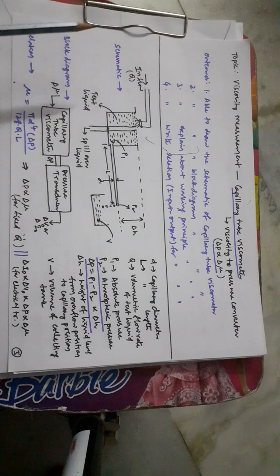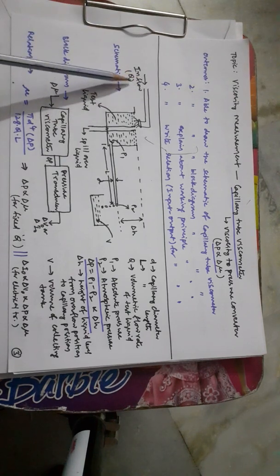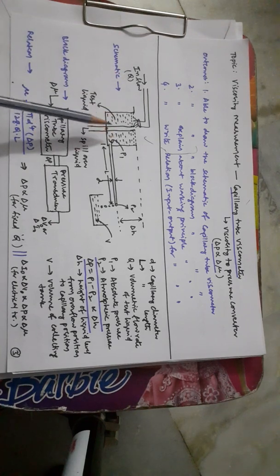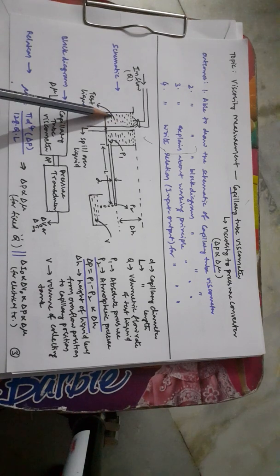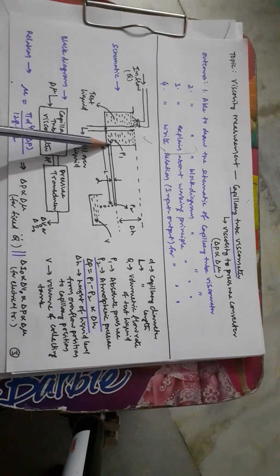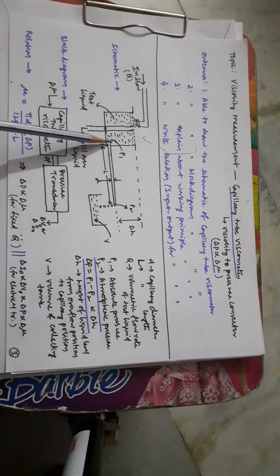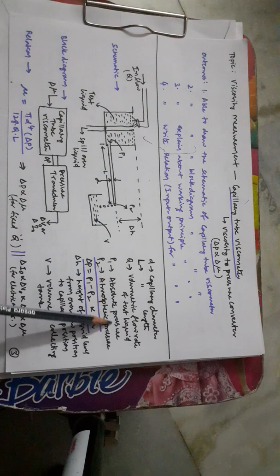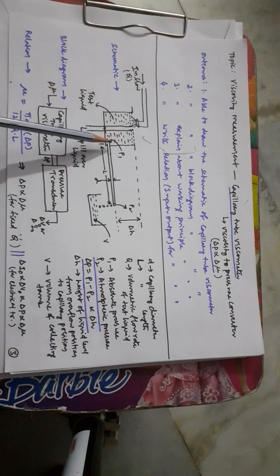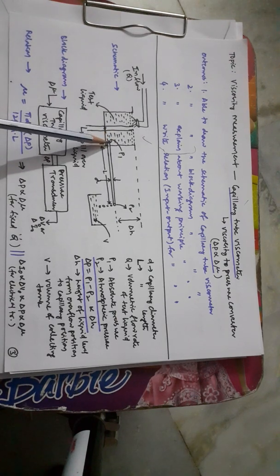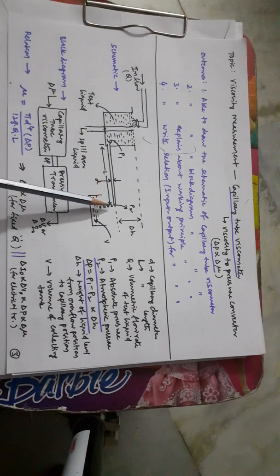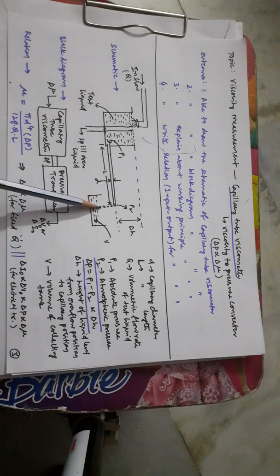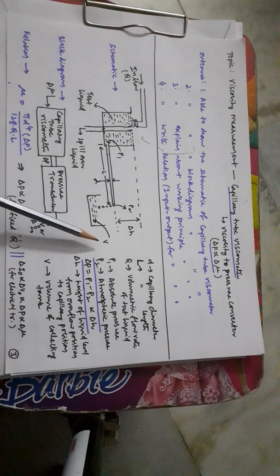Here is the schematic of the capillary tube viscometer. The inlet has a flow rate Q for the test liquid whose viscosity is to be measured. When the liquid overflows, spillover liquid exits to maintain a fixed standard level in the buffer tank. The output of the buffer tank connects to a capillary tube of length L and diameter d. The fluid slowly flows out and collects in a collecting tank of volume capital V.